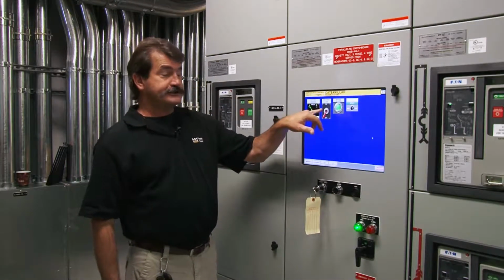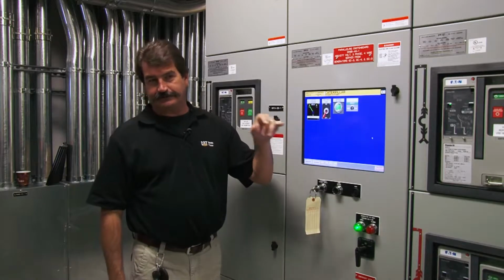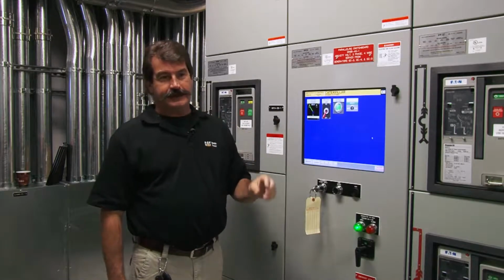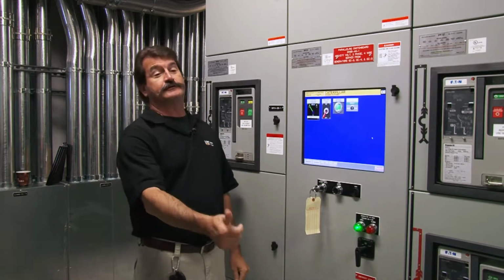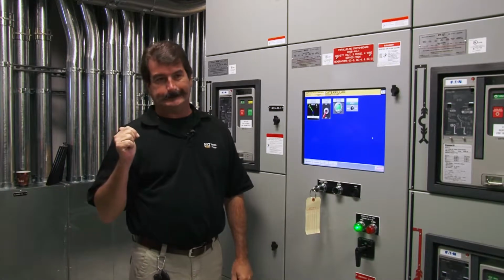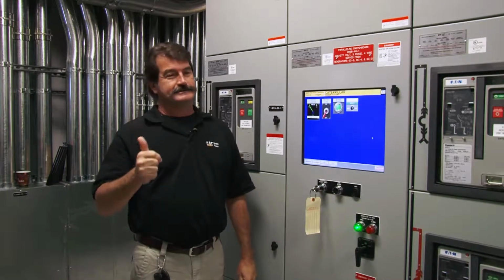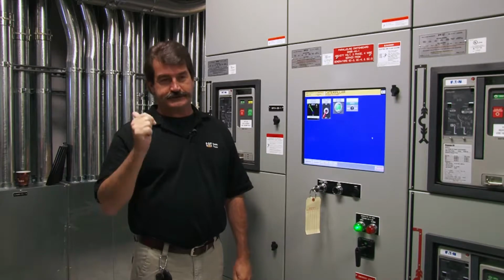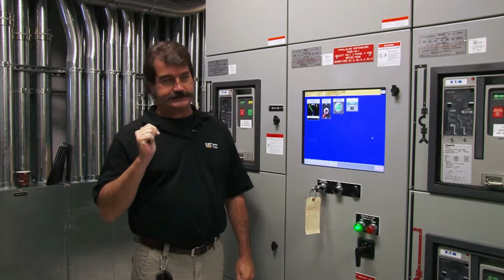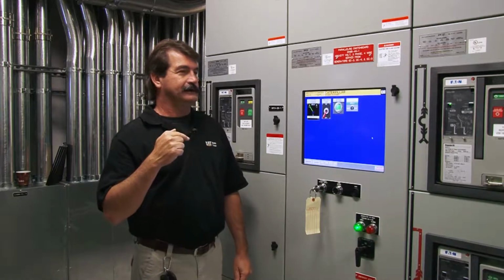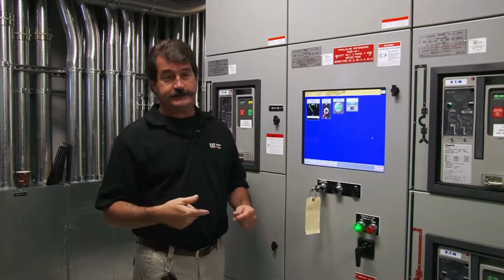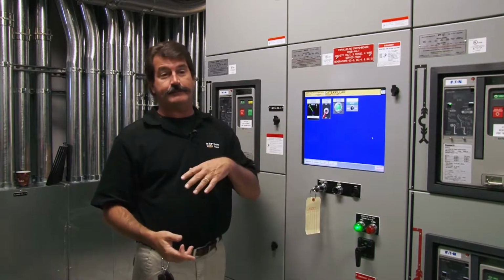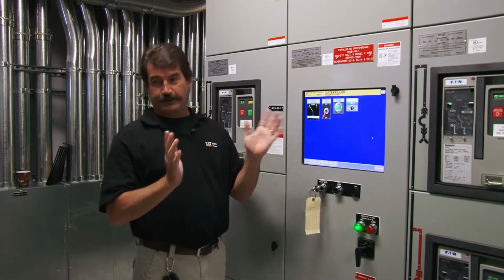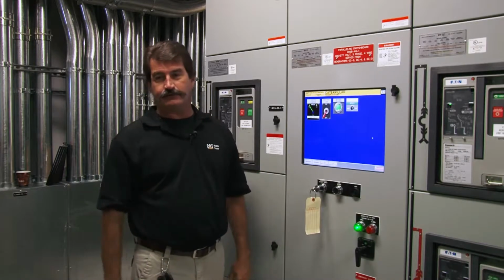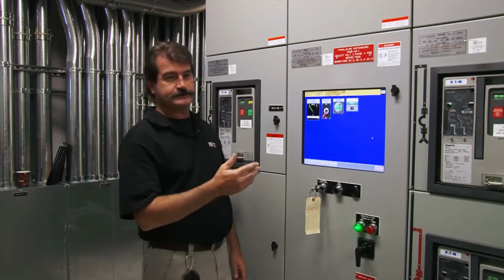If you go test with load, that's going to send a signal to that ATS, and it's going to send a signal back to us to say, okay, it's going to give us a gen run signal. Whenever it does, we're going to start the gens, and once we start the gens, it's going to flop over. So you're going to have that brief interruption of power whenever it flops over to go to the emergency on that one.